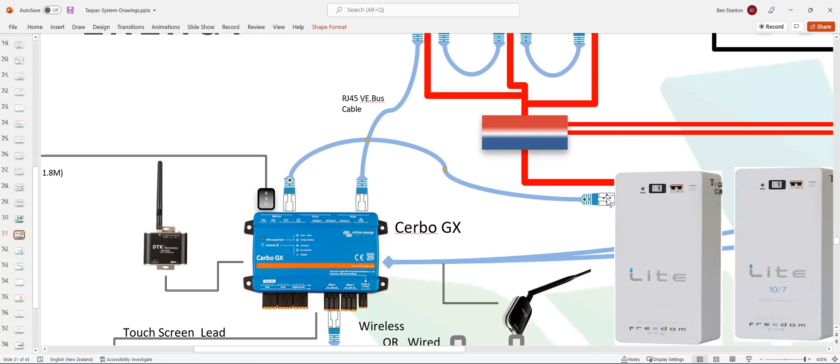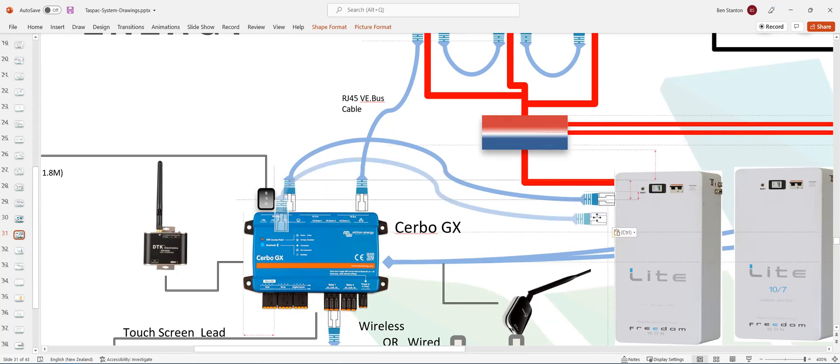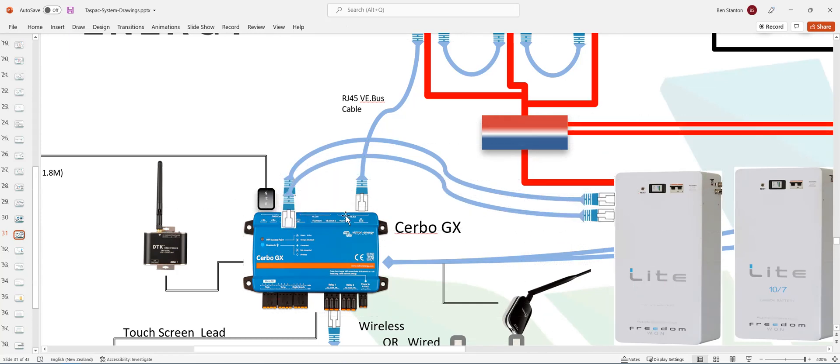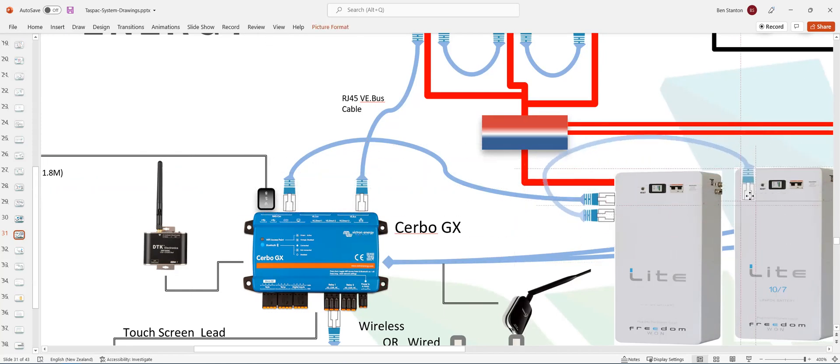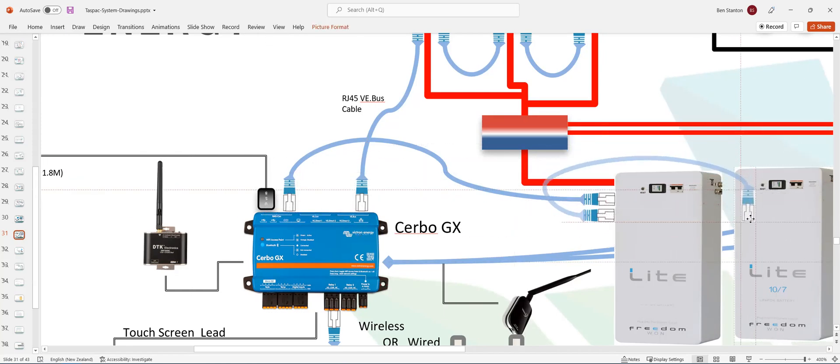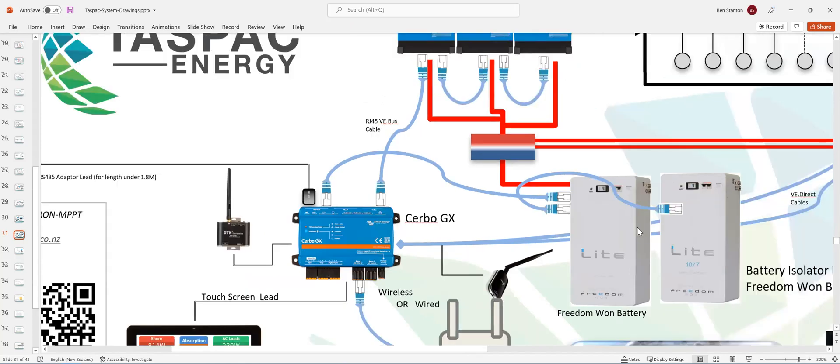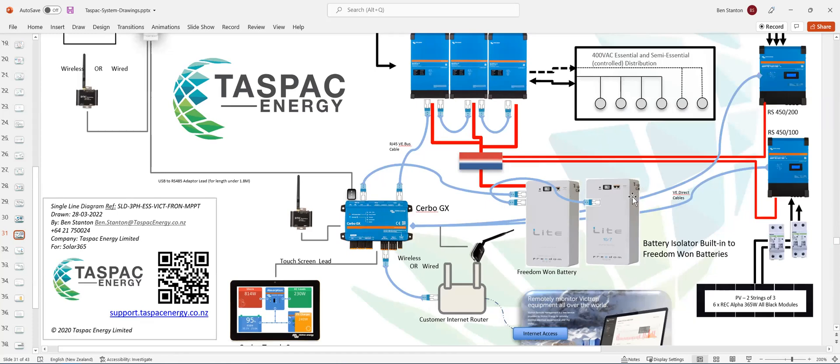And they are daisy-chained. So these units here basically connect from one to the other. The batteries will just daisy-chain to each other. Pretty simple. You'll see the ports there. And you just connect the two, the data cables, one to the other. And then the end, the last battery, has an end-of-line resistor in it, as does the port on the Cerbo GX.